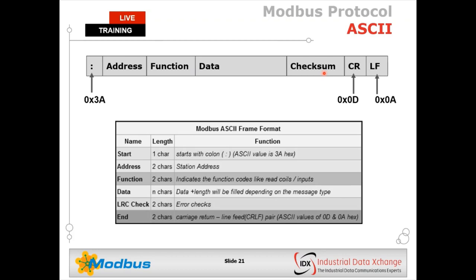Modbus ASCII is similar to Modbus RTU but uses ASCII encoding. The checksum is an LRC type. Start and end delimiters are not silence periods — it starts with a colon (0x3A) and ends with a carriage return line feed (0x0D, 0x0A). Modbus ASCII is not as popular as RTU because frames are substantially longer — it uses double the data to transfer the same information. It's human-readable without decoding but less efficient, though it uses the same addressing and function mechanisms as RTU.